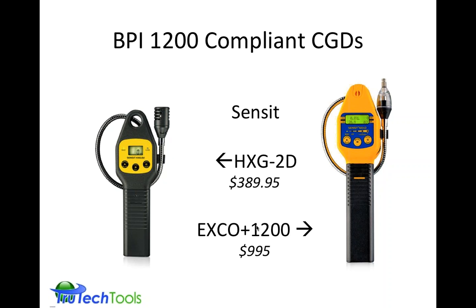The EXCO Plus 1200 is actually the big brother to the HXG2D in that it combines all the features of that, plus it actually covers the BPI 1200 requirements. And in terms of doing the gas leak detection, the CO air-free or combustion test, and also doing the oxygen depletion for OSHA, the LEL for OSHA, it's a multi-purpose meter that covers the OSHA requirements and the BPI requirements. Keep in mind, if you do have your authority saying you have to do more than BPI 1200, make sure you understand what's on your checklist and you pick the correct device. But this EXCO Plus 1200 was designed specifically for the purpose of complying with the OSHA and the BPI 1200 requirements.